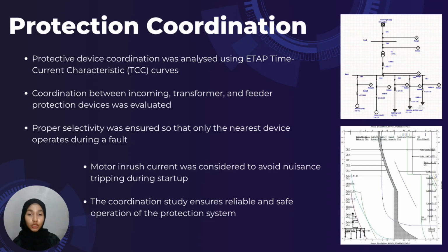Motor inrush current during startup was also considered in the relay and breaker settings to prevent nuisance tripping, especially for large motor loads. Overall, the protection coordination study confirmed that the system is safe, reliable, and well coordinated, ensuring effective fault isolation and continuity of supply.